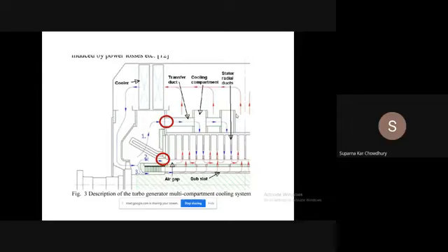The product of the specific heat and the density is approximately 0.98, that is almost equal to 1. So the heat capacity of air and hydrogen is almost the same, but the main advantage of hydrogen is that, being light, the windage loss of the machine will reduce manifold.